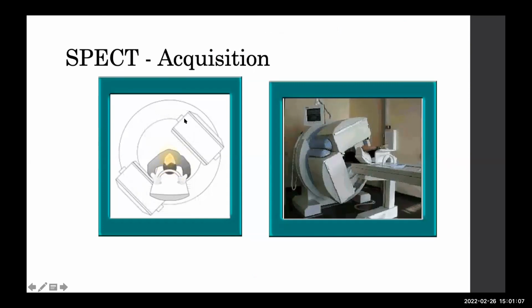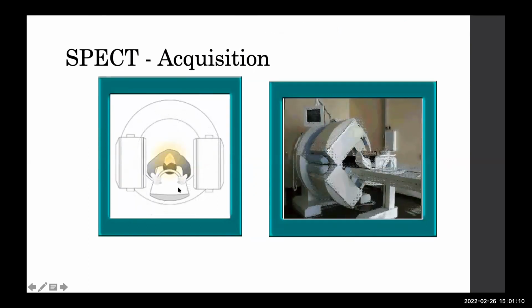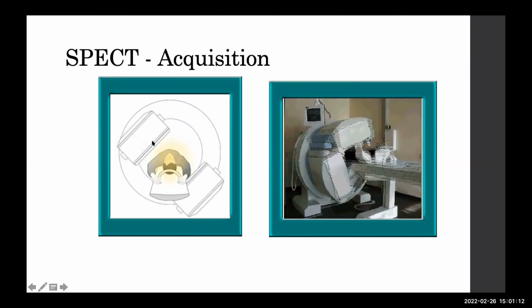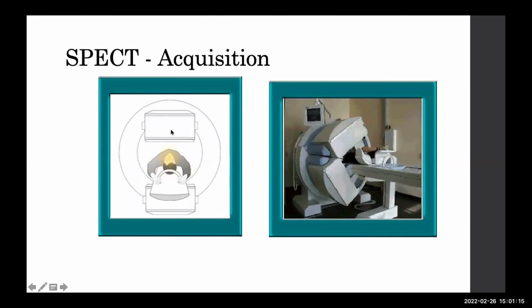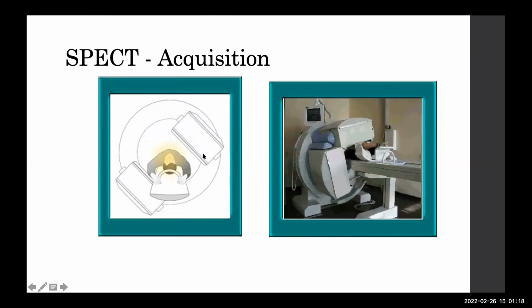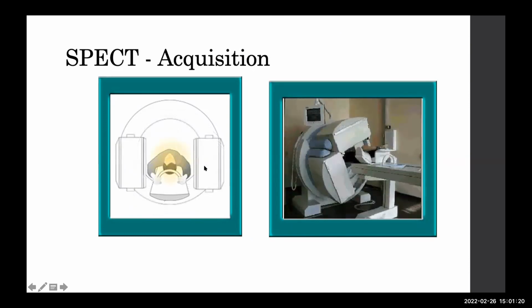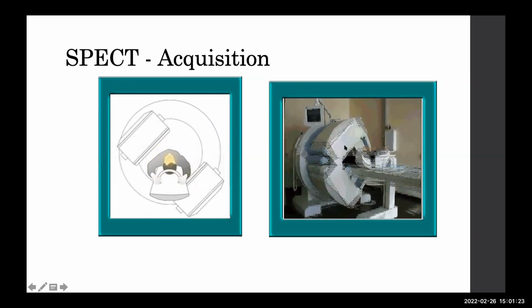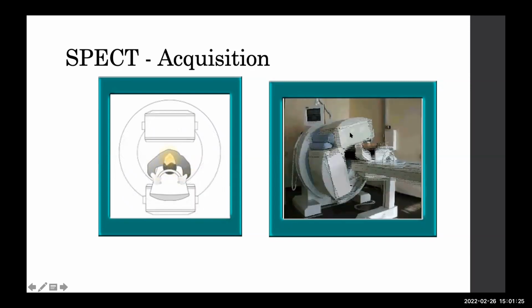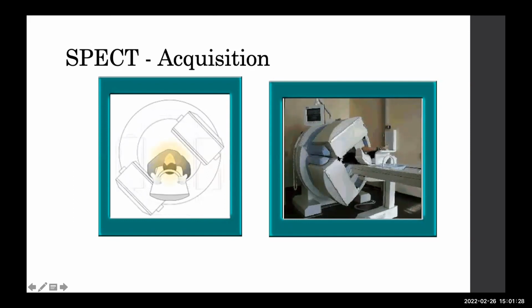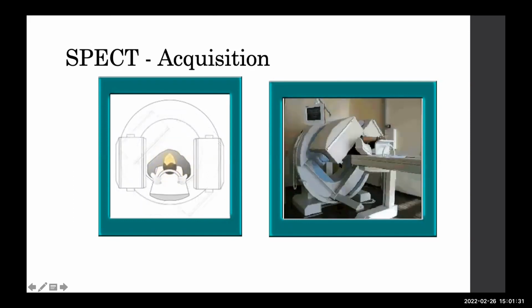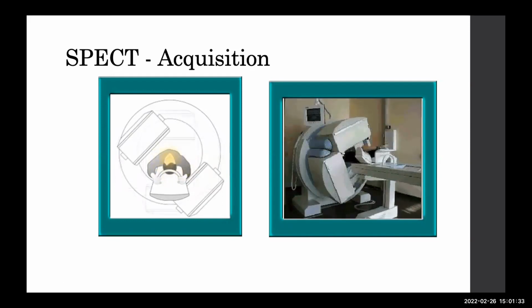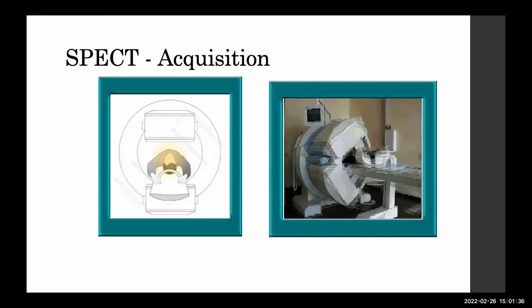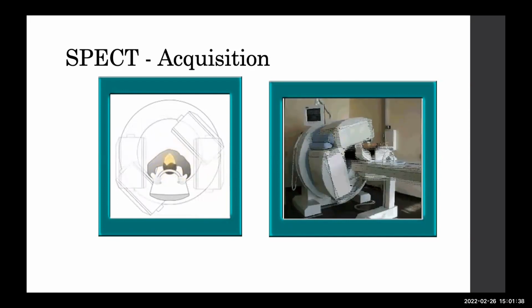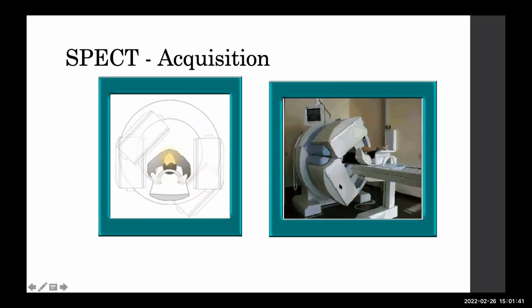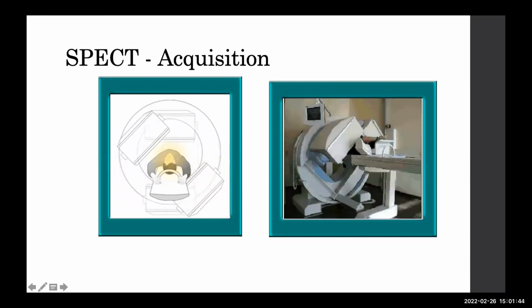You can see here in a cine loop how the dual detectors are moving around the patient, and the radiation is emitting from the patient, and the detectors are moving continuously, gathering the data around the patient on a particular organ of interest. Like in this patient, the angle is 90 degrees, where the two detectors are acquiring the data around the heart and getting the myocardial perfusion SPECT study. So depending upon which organ, you can have a specific angle, and this is a 180 degree acquisition, and this is a 90 degree acquisition, with dual detector angulation while the SPECT study is going on.